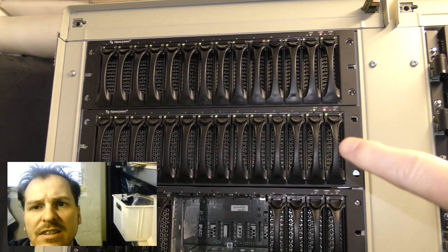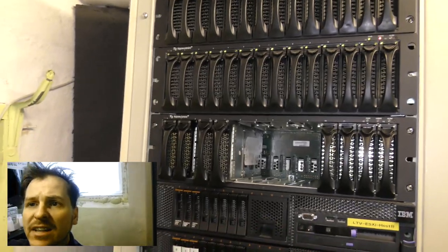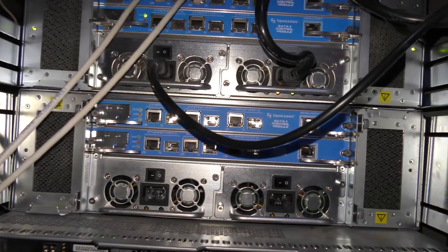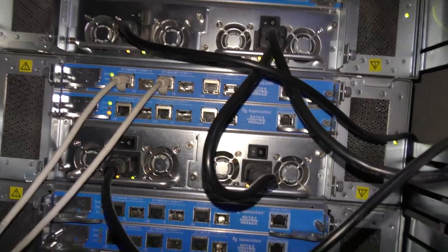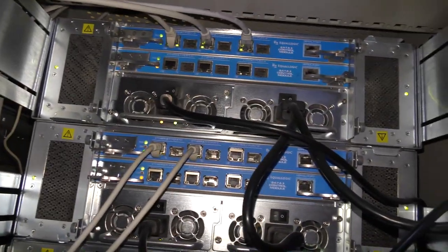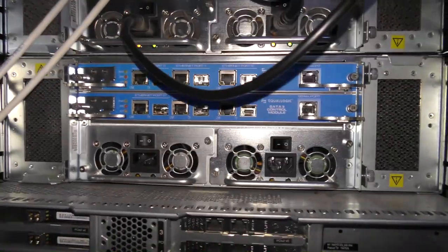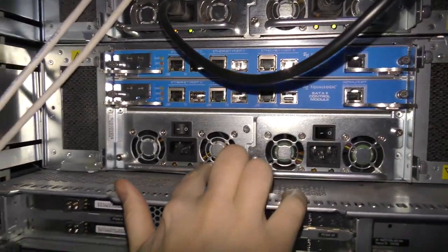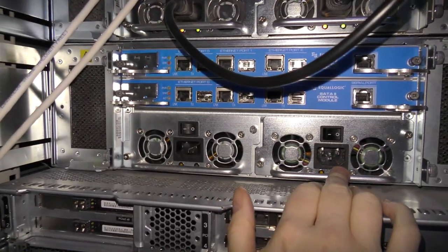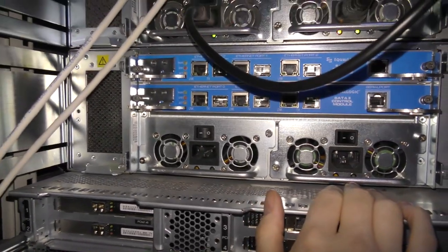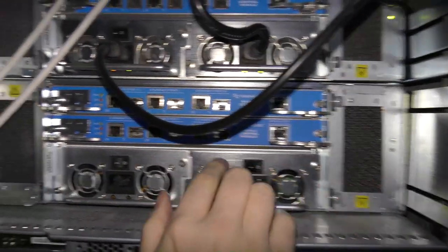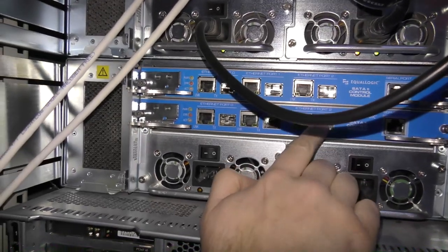Let's go to the back and see what's back there. Here is the back of the devices. There are three of those - one up there, one there, and one there. Each of them is just pointing at the bottom one. They each have two power supplies, so they have redundant power. They have redundant fan blowers, one in each side here, and they have redundant controllers.